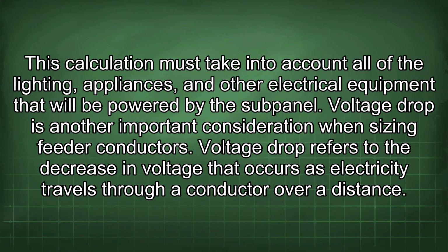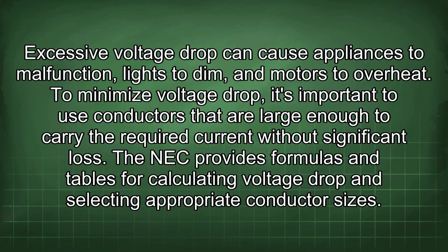This calculation must take into account all of the lighting, appliances, and other electrical equipment that will be powered by the subpanel. Voltage drop is another important consideration when sizing feeder conductors. Voltage drop refers to the decrease in voltage that occurs as electricity travels through a conductor over a distance. Excessive voltage drop can cause appliances to malfunction, lights to dim, and motors to overheat. To minimize voltage drop, it's important to use conductors that are large enough to carry the required current without significant loss. The NEC provides formulas and tables for calculating voltage drop and selecting appropriate conductor sizes.